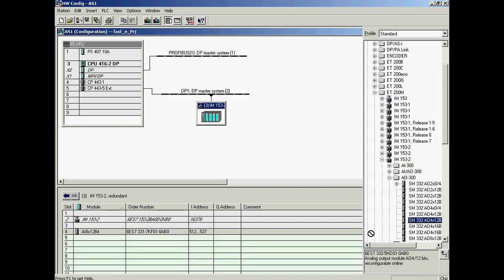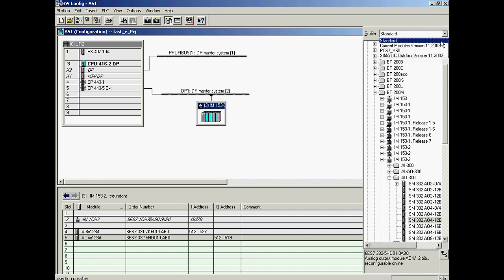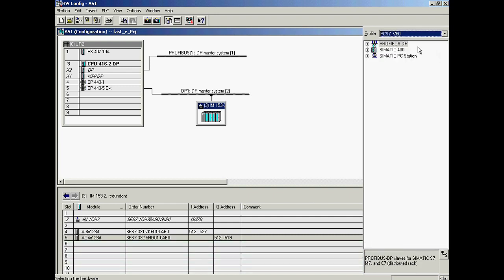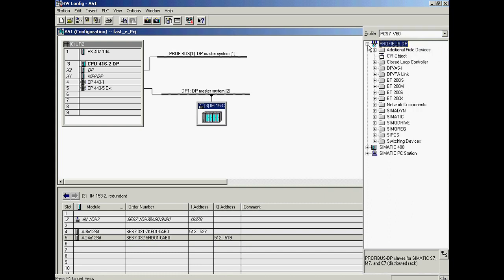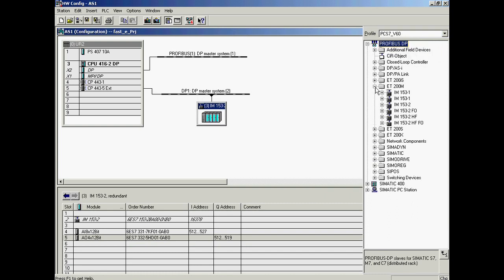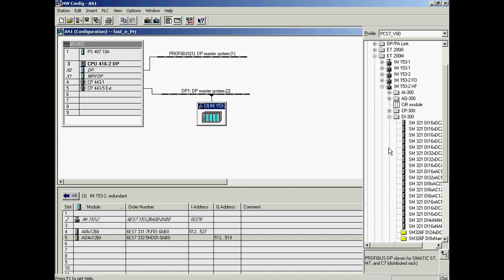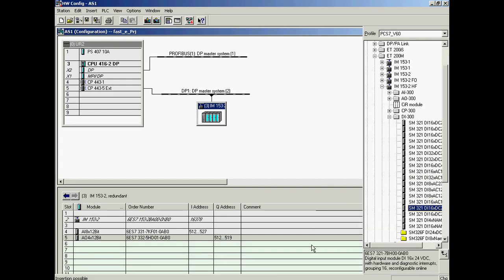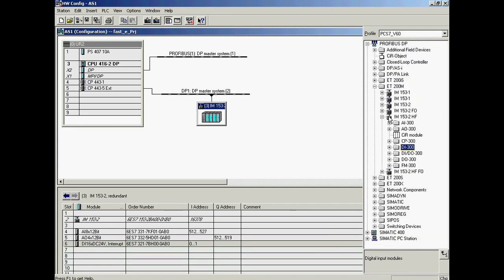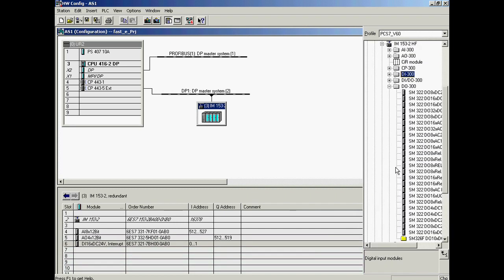However, it is recommended to work with the PCS7 V6.0 catalog, since it contains the subset of available hardware modules that are optimized for use with PCS7 V6.0 and therefore enables you to work more efficiently. The digital input module is included in the PCS7 V6.0 catalog and is plugged into slot 6. The last module to be configured is the digital output module in slot 7.